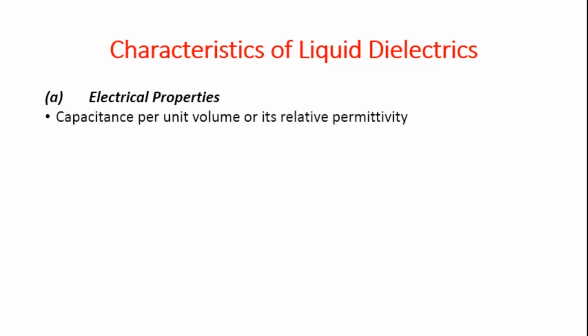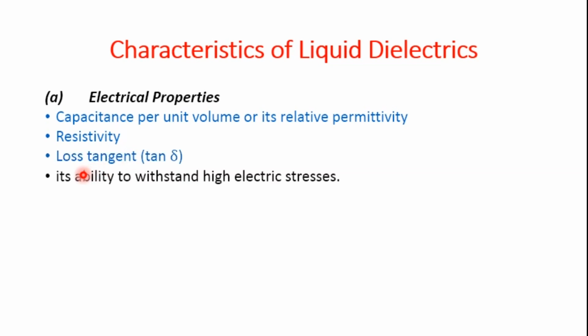Coming to the characteristics of liquid dielectrics, they should possess good dielectric properties, excellent heat transfer characteristics, and must be chemically stable under the range of conditions in which the equipment operates. Let us briefly discuss these: electrical properties, heat transfer characteristics, and chemical stability. First, the electrical properties. These are essential in determining the dielectric performance of liquid dielectrics: capacitance per unit volume, or relative permittivity, then resistivity, then loss tangent, or generally the power factor, which is an indication of power loss under AC applications.